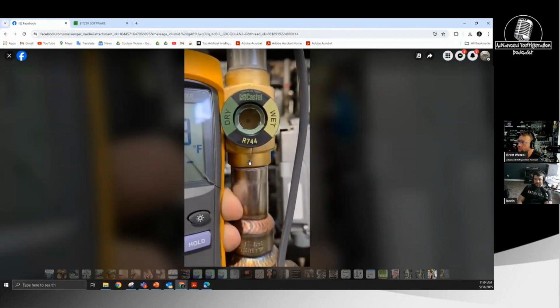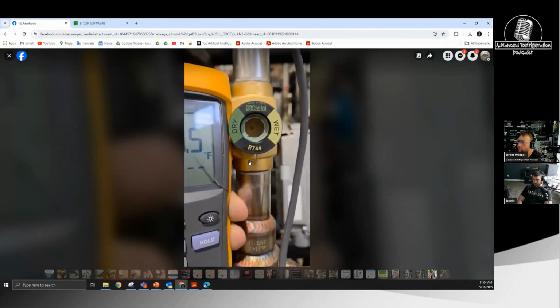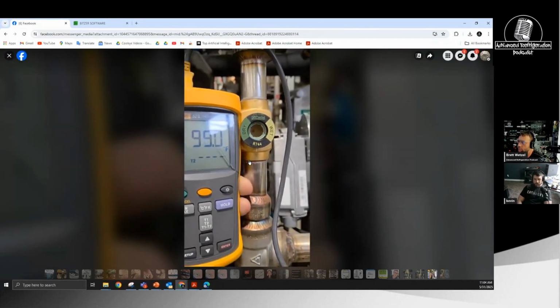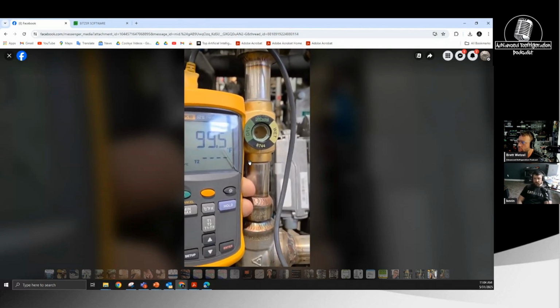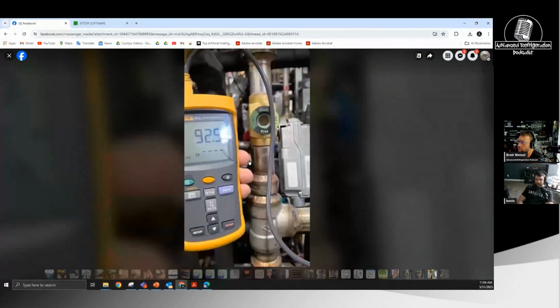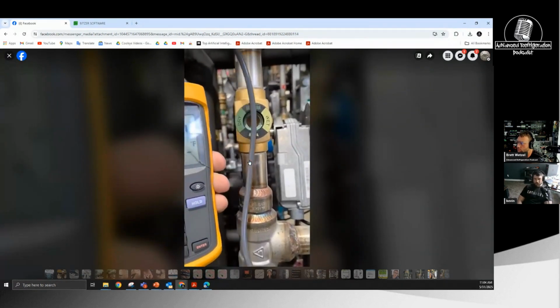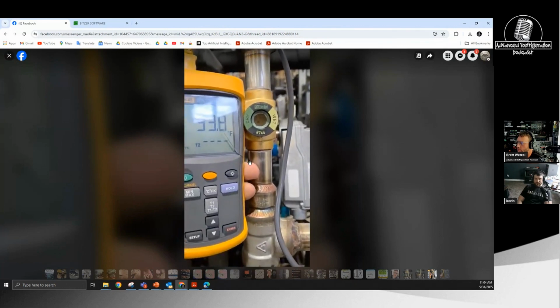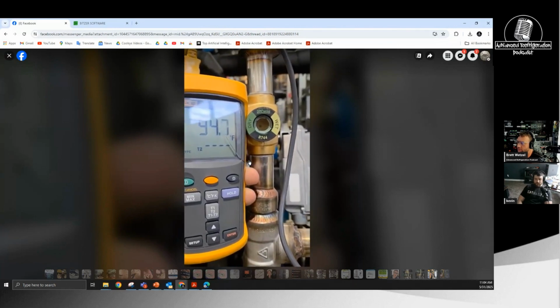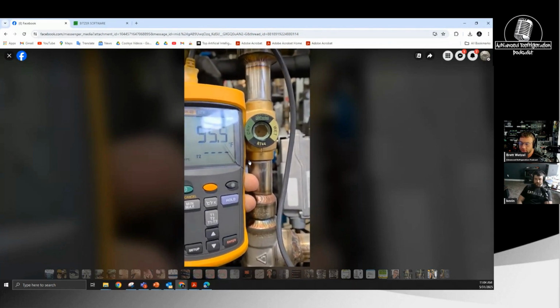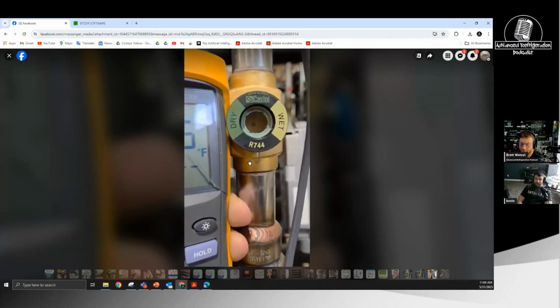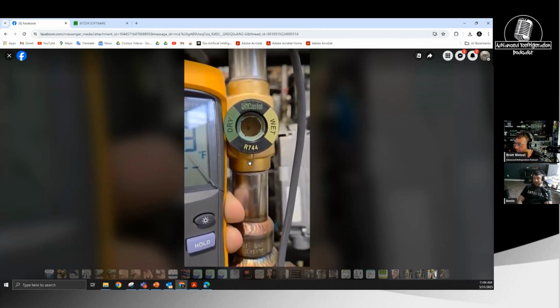And while this is happening, we're all at like 1250, 1350 - I think at the time this one was limited to 1350 psi as the max GC gas cooler pressure. Look how clear that inlet sight glass is. Supercritical fluid is supposed to be clear. It looks almost like a little bit like a lava lamp. That looks like liquid to me. Okay.